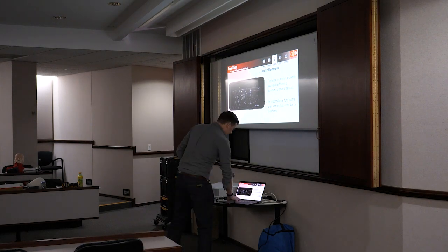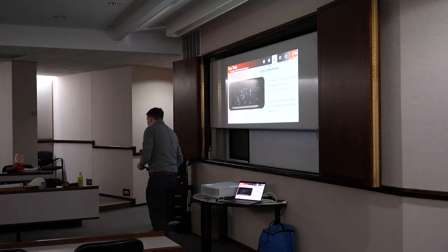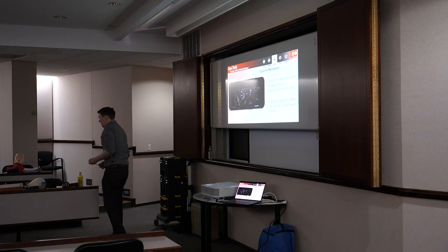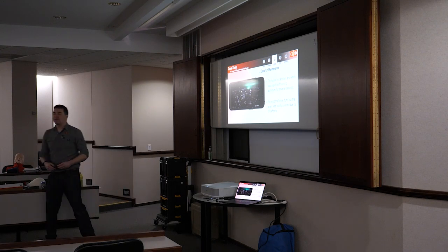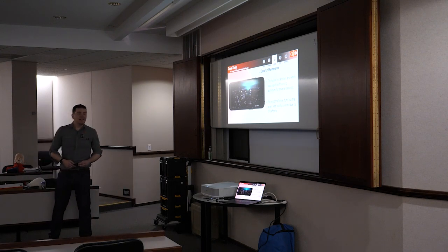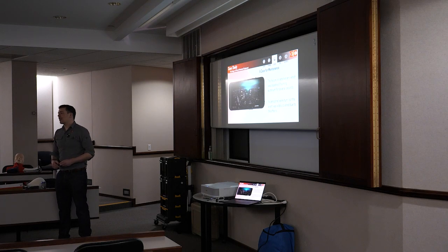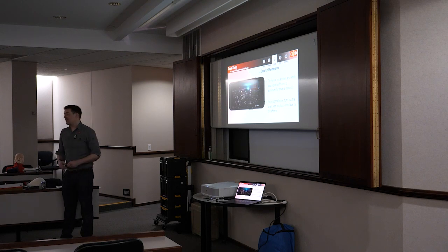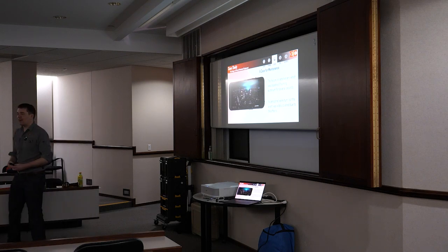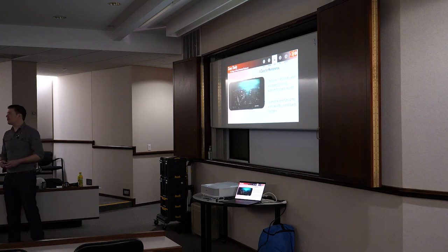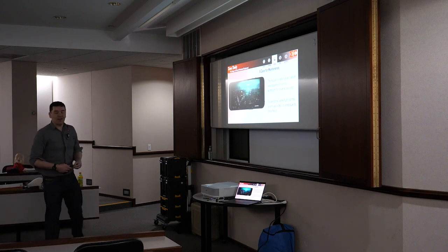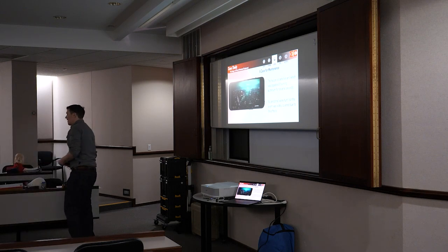Make sure that's playing. Again, this is a reason for maintenance and for the things that we do, because failure happens every single day. This is in real time, and we won't see the whole video since it's 2 minutes long. A Con Ed substation burned aluminum brightly for almost 2 minutes straight without a single protective device interrupting that flow of current and stopping it.